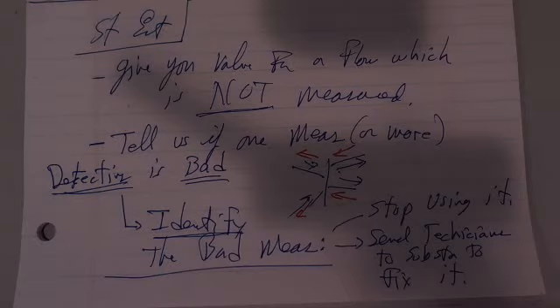Otherwise, they're making decisions on measurements that are bad. Suppose they're looking at a power flow on a line, checking if it's getting close to its limit. The limit is 250 megawatts, and it looks like it's only at 210, so they think they're fine. But in fact the measurement is bad, and it's not actually flowing at 210, it's 280, and it's overloading. So you're making a bad decision, and something can happen because you're getting a false picture from a bad measurement.